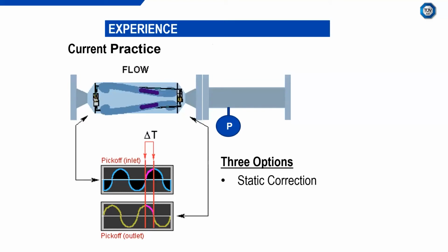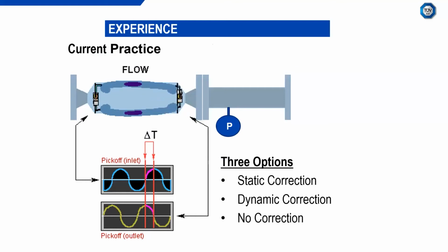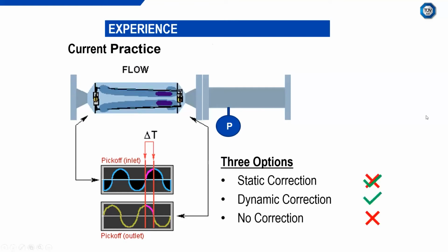Now, in terms of pressure correction, you have three options. What we've got here, you can see that capital P, is meant to be a pressure gauge located downstream as the flow is going from left to right. You can have a static correction, a dynamic correction, or apply no correction. Now, what do we recommend? I think the recommendation would be to apply a dynamic correction. The static correction would also work, hence why we have a tick and a cross, but it's not ideal.